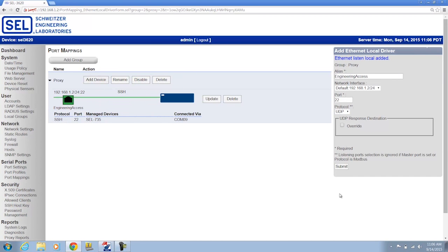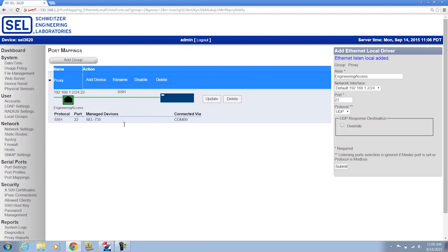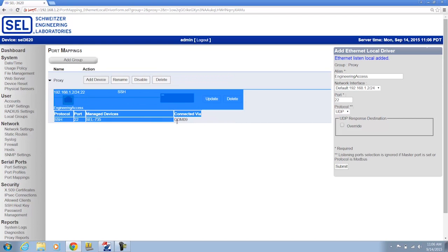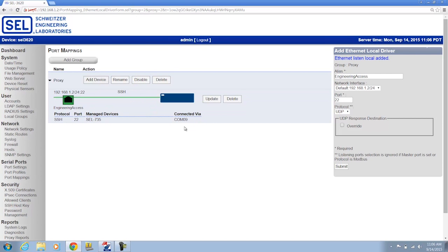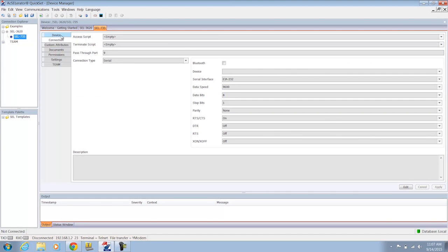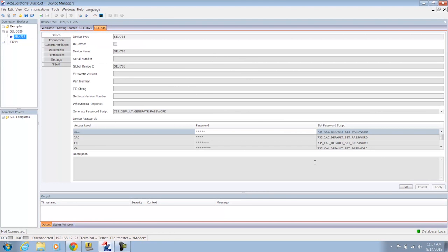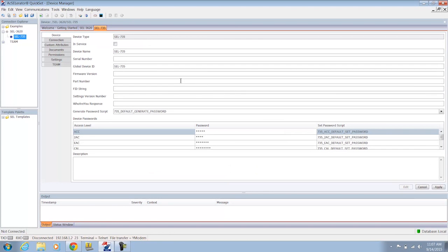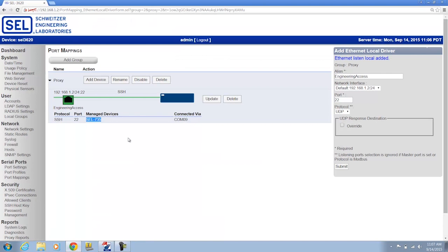So now, in a previous video, we actually uploaded the connection directory to the 3620, so we know we have a connection directory on this device already. And when you add a scripting-enabled master port on the 3620, it'll sense that connection directory and show you the device that's already been added via that connection directory. So it's showing us that we have that SEL735 relay, and that matches the global device ID on the SEL relay in the connection directory. So this SEL735 here matches what is listed on the web interface of the 3620. And it shows that it's connected via serial port 9 on the back of the SEL3620.